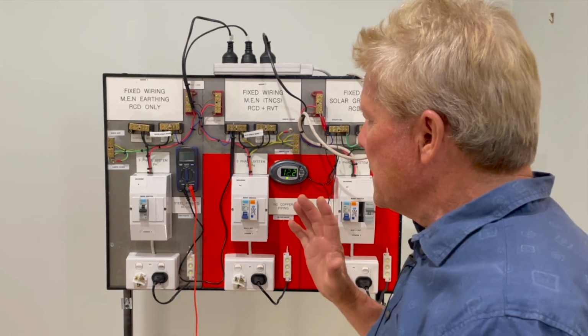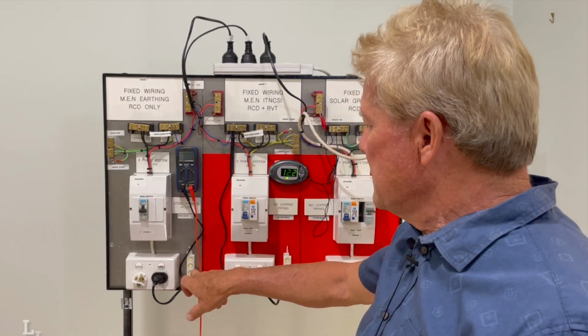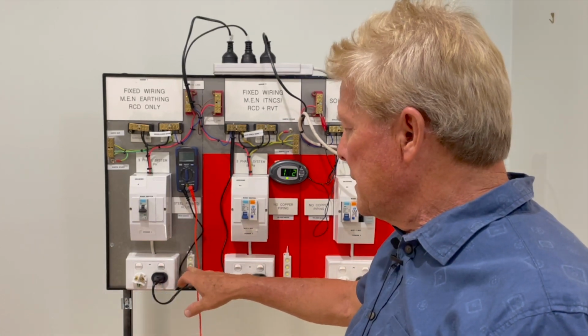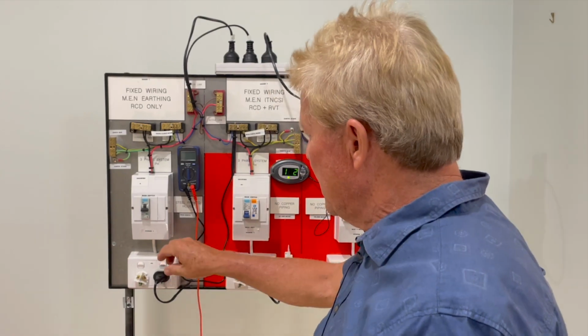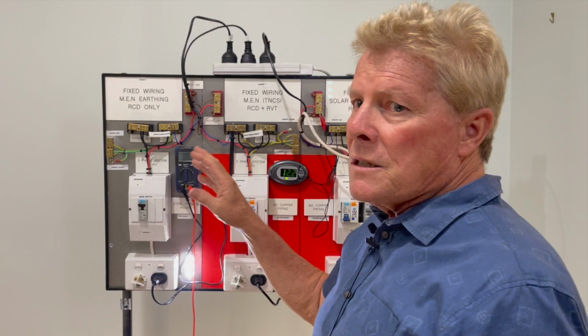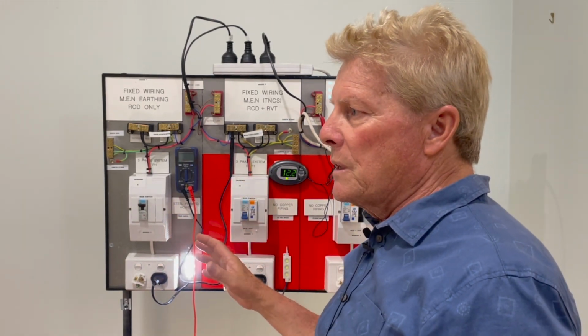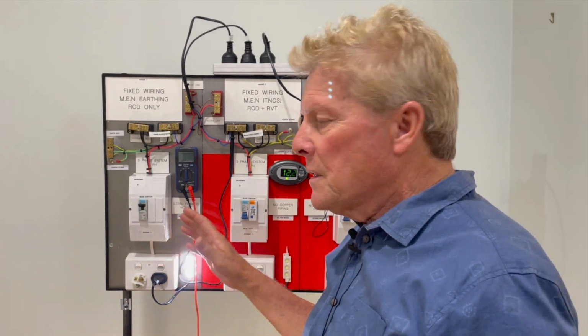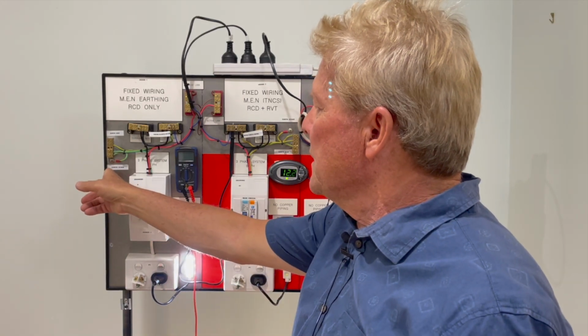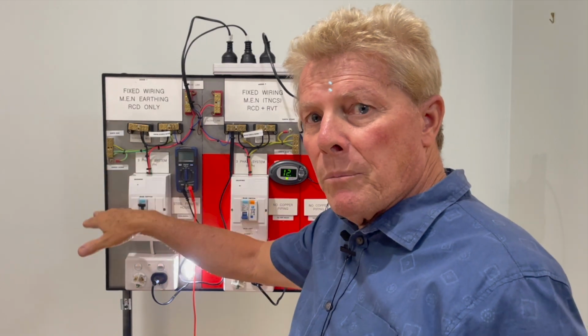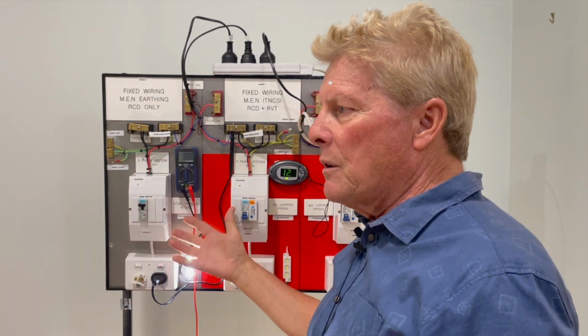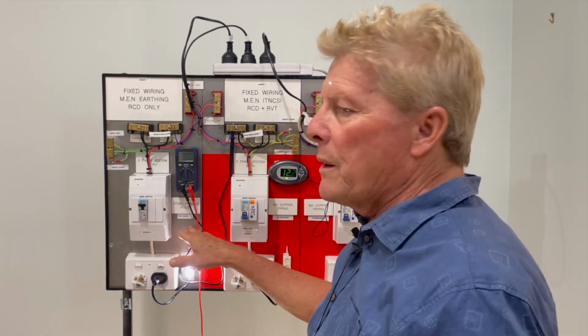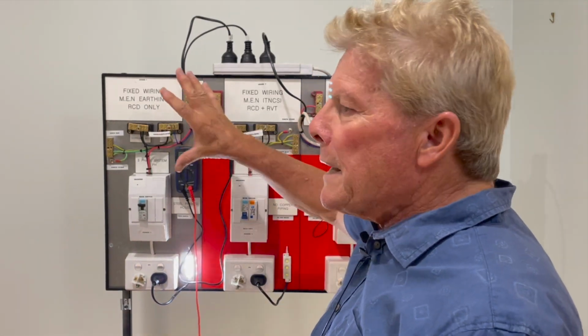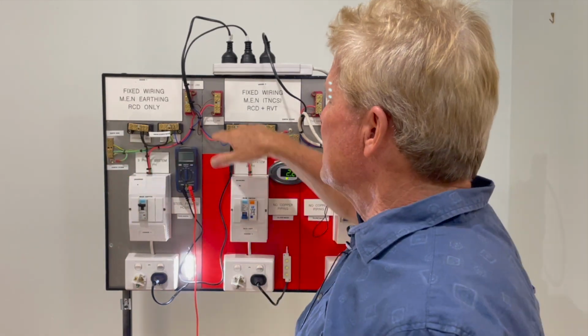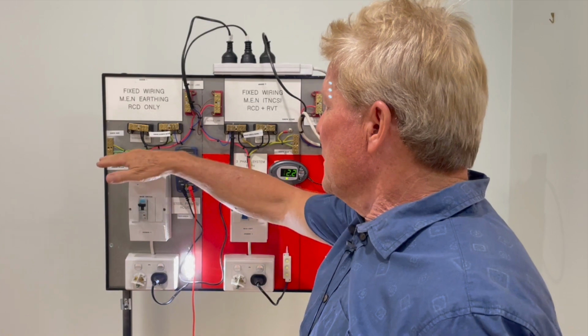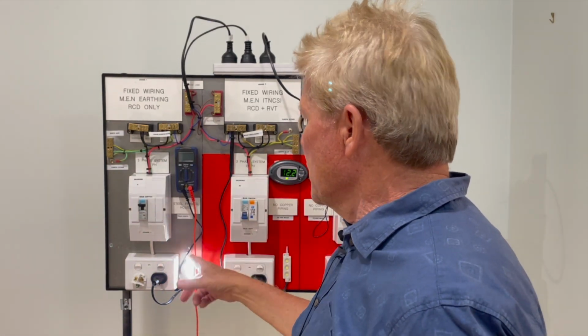So we're going to get stuck into it. Everything's ready to go. We've got our little loads down here on each circuit. They're just LED loads because the voltage is right down low. So if we turn on house one, it is as per the drawings that we have in all our documentation. It's got the copper piping, which is represented over here. This is our earth stake. The aluminium is your copper piping, your whole gas piping, all your extraneous metal components. That's represented in this little section here. So it's laid out exactly the same as our drawings. You've got your yellow zone up here, which is your utility zone, and you've got your red zone down here, and house one's turned on, and we're using the lights and power.